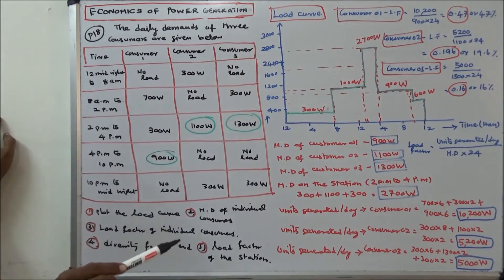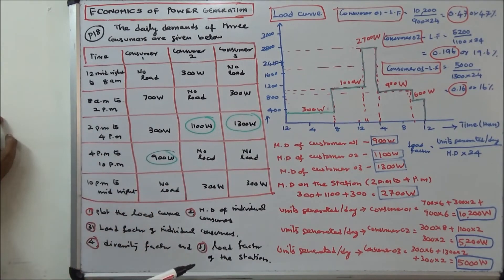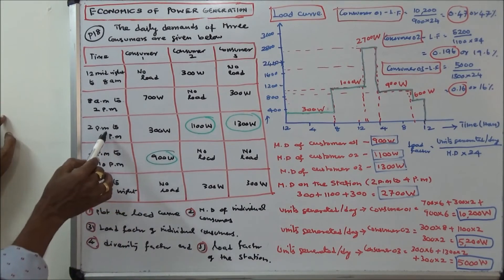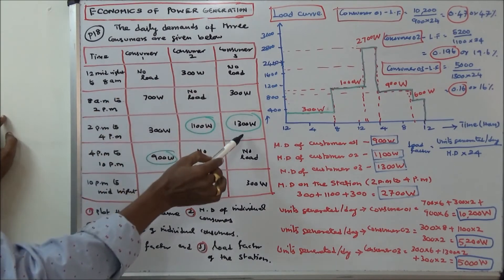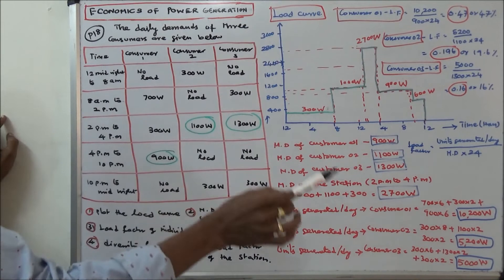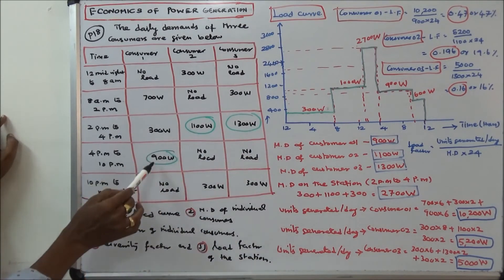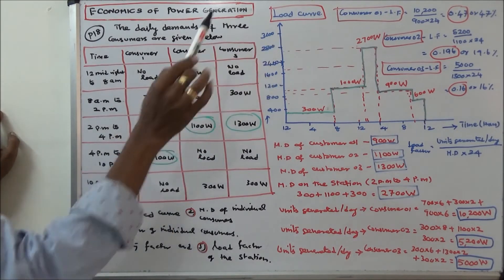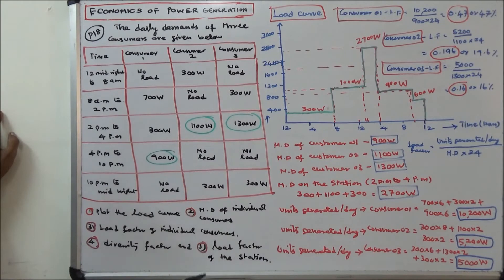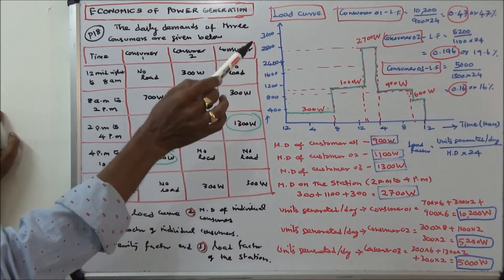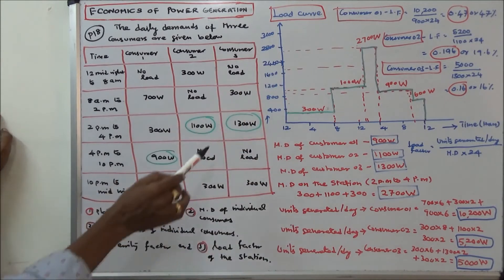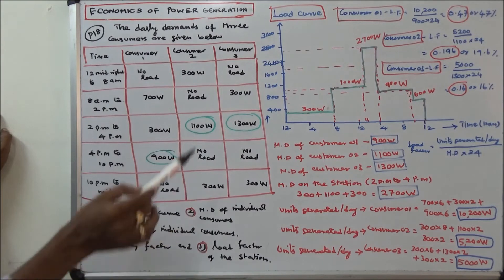Load factor equals units generated per day divided by maximum demand times 24. Maximum demand: Consumer 1 = 900 W, Consumer 2 = 1100 W, Consumer 3 = 1300 W. Load factor Consumer 1: 10,200 ÷ (900×24) = 0.47 or 47%. Load factor Consumer 2: 5,200 ÷ (1100×24) = 0.196 or 19.6%. Load factor Consumer 3: 5,000 ÷ (1300×24) = 0.16 or 16%.